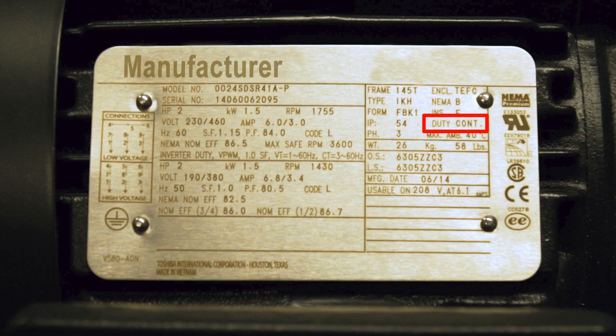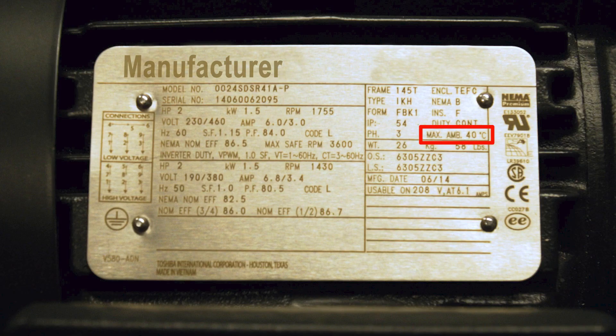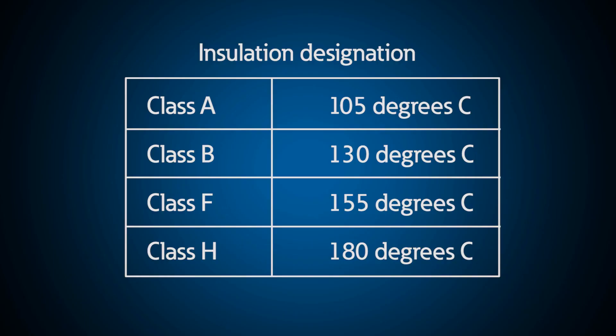There is a time or duty rating, which is how long the motor can run at rated load. Usually you'll see CONT, meaning that it can do so continuously. You'll also see the max ambient temperature for the surrounding environment that the motor can be in. There is an insulation designation given by a letter A, B, F, or H. The higher the letter is in the alphabet, the higher the temperature the windings can withstand for longer periods of time.